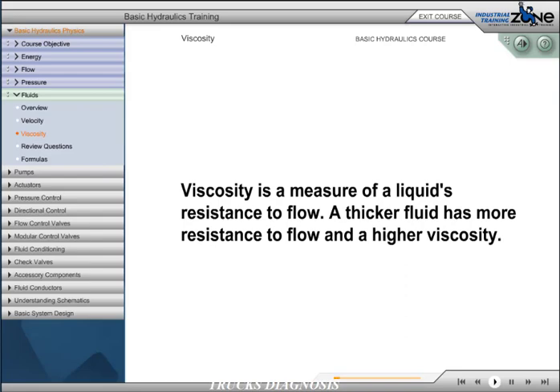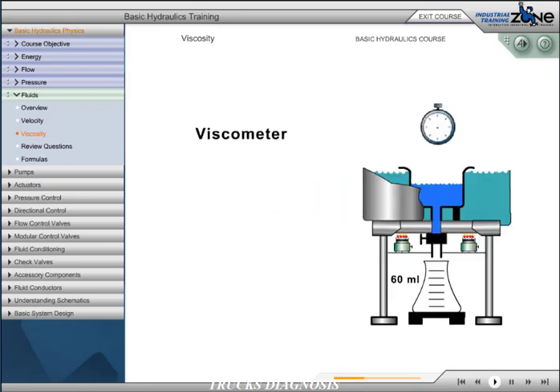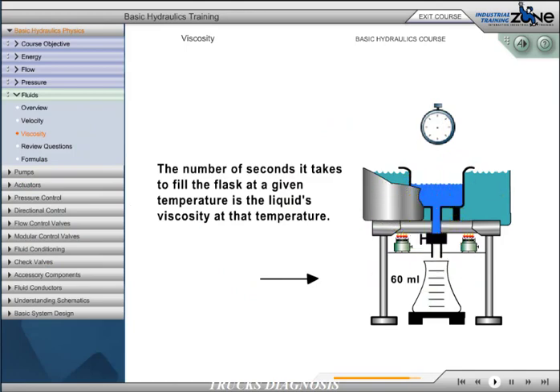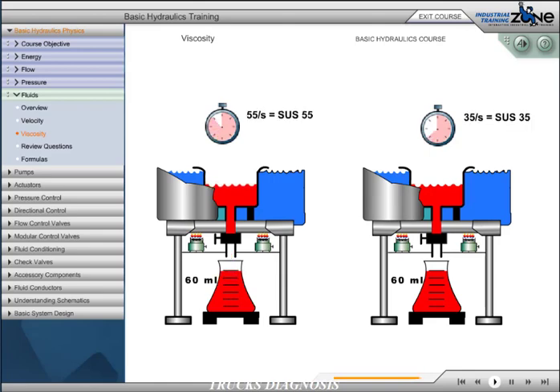Viscosity is a measure of a liquid's resistance to flow. A thicker fluid has more resistance to flow and a higher viscosity. Viscosity is affected by temperature. As a hydraulic fluid's temperature increases, its viscosity or resistance to flow decreases. A viscometer, the device used to measure a liquid's viscosity, consists of a small reservoir surrounded by a water bath used to heat and maintain the liquid at a constant temperature. There is a small orifice below the reservoir through which the liquid can pass once it is heated to a specified temperature. A stopwatch is used to determine how much time it takes to fill a 60 milliliter flask. The number of seconds that it takes to fill the flask at a given temperature is the liquid's viscosity at that temperature. As illustrated, the fluid on the right has a lower viscosity than the fluid on the left.